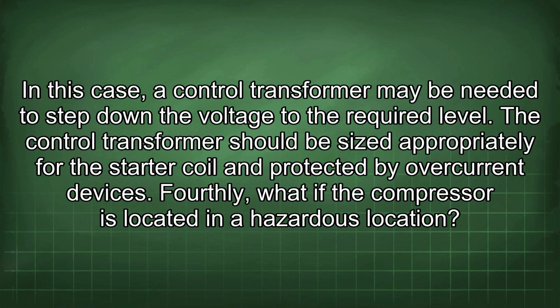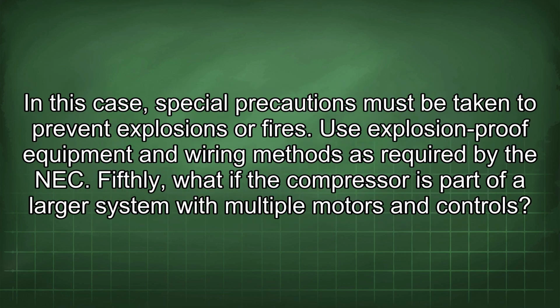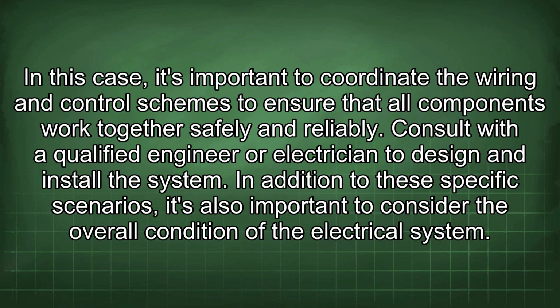Fourthly, what if the compressor is located in a hazardous location? In this case, special precautions must be taken to prevent explosions or fires. Use explosion-proof equipment and wiring methods as required by the NEC. Fifthly, what if the compressor is part of a larger system with multiple motors and controls? In this case, it's important to coordinate the wiring and control schemes to ensure that all components work together safely and reliably. Consult with a qualified engineer or electrician to design and install the system.